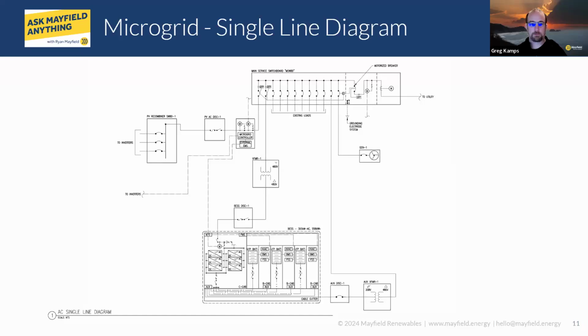Yep. This was a pretty large project. I believe that main was either 2,000 or 4,000 amps, so doing a motorized breaker on that made sense, where a contactor at that scale didn't. ASCO just came out with the first off-the-shelf grid isolation device, and I think that currently goes up to 600 amps at 480 volts. They're going to be coming out with additional sizes.